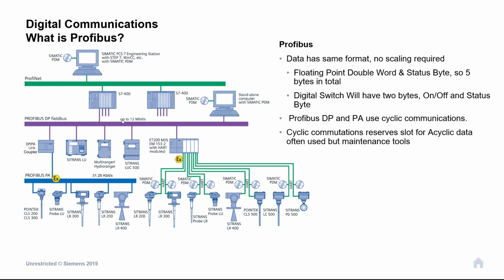And then the nice bit at the end is something called a status byte. This is all the error code information contained within the instrument, transmitted in a uniform manner. And this is the information that tools like SIMATIC PDM will look at.